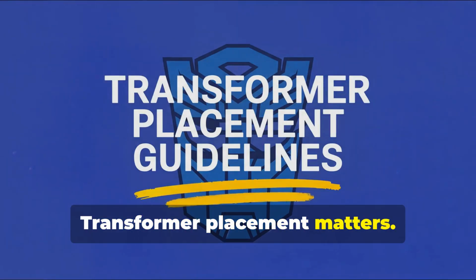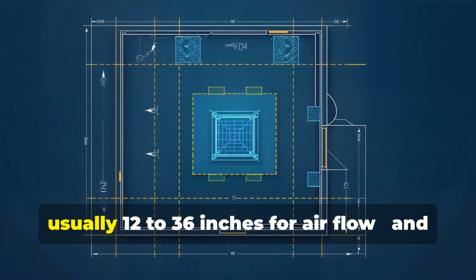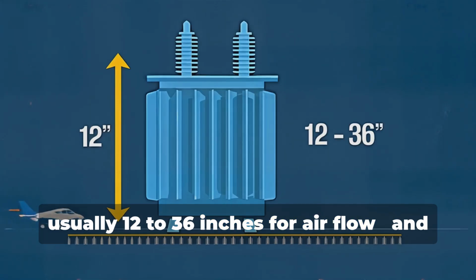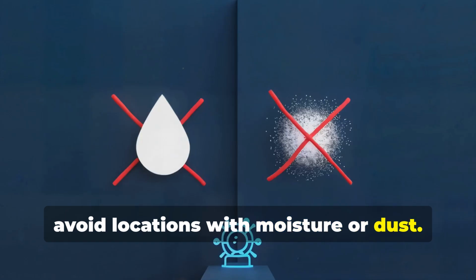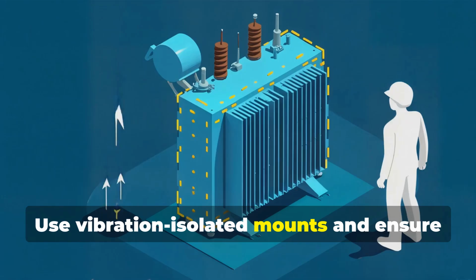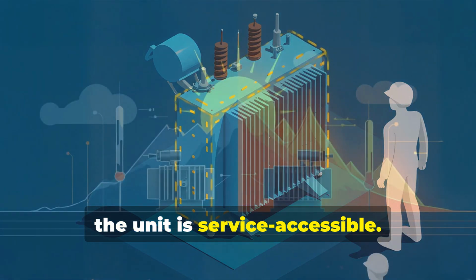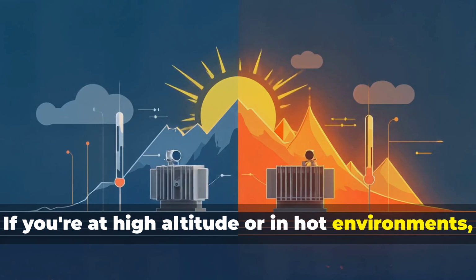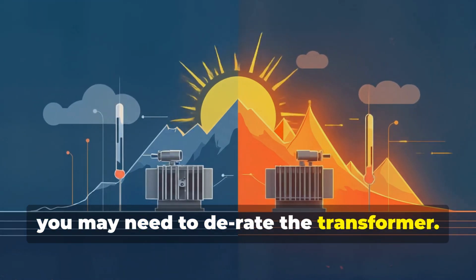Transformer placement matters. Always provide plenty of clearance, usually 12 to 36 inches for airflow, and avoid locations with moisture or dust. Use vibration-isolated mounts and ensure the unit is service accessible. If you're at high altitude or in hot environments, you may need to derate the transformer.